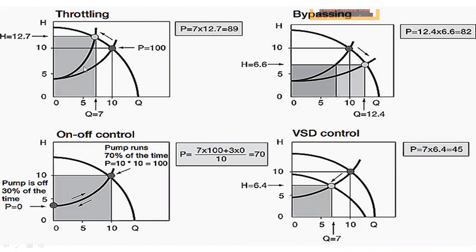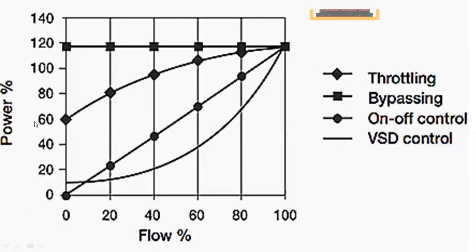In terms of power consumption: throttling consumes approximately 89%, bypassing 82%, on-off control 70% (since the pump runs about 70% of the time), and variable speed drive only 45%. The area under the pump curve directly represents power consumption, making variable speed drive control the most efficient method for varying flow requirements. That covers pumps — their operation, control, and instrumentation. Thank you very much.